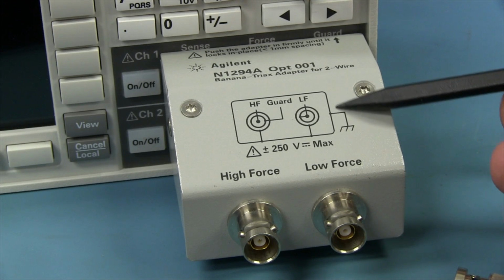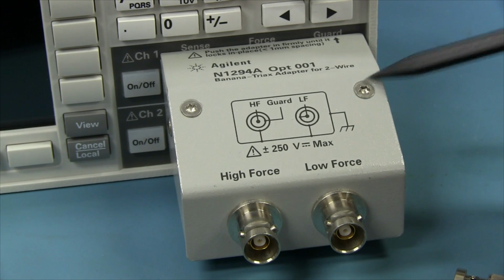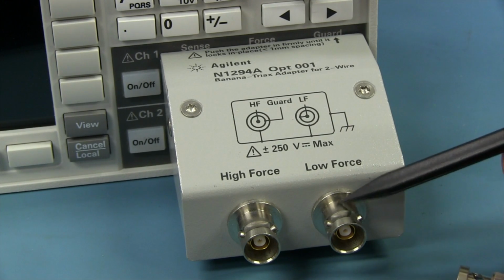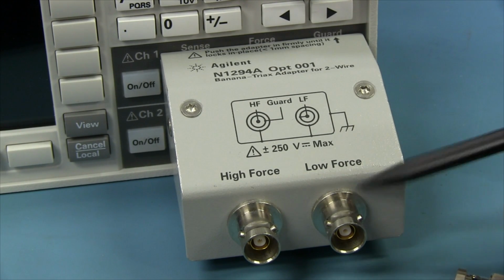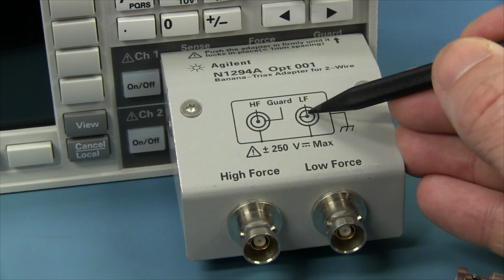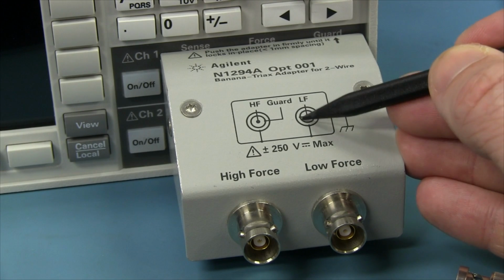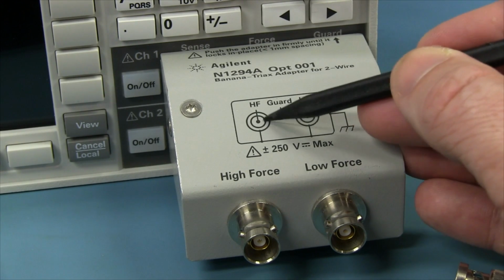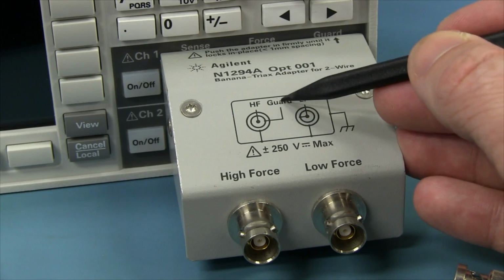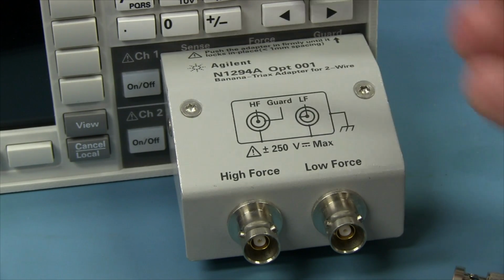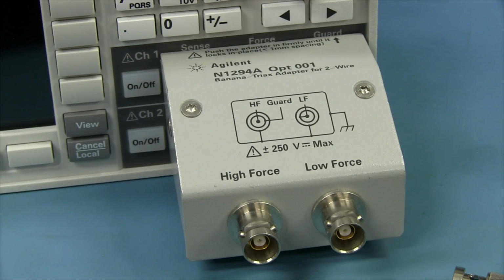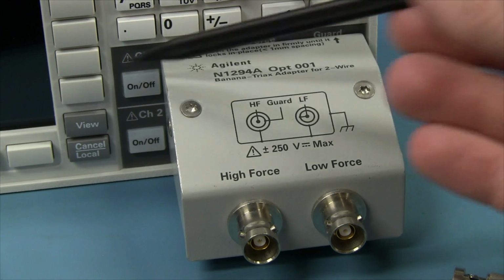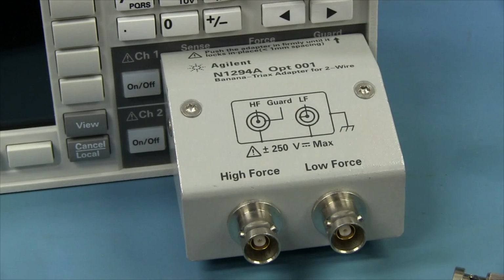And of course, you can see that this whole outer box, and the outer part of the coax, is connected through to your mains earth, so that stops any mains hum getting in. And then inside your triaxial, the shield inside there is connected through to your guard terminal, which is your circuit common inside your instrument. So therefore, you get double shielding on this thing, 50 hertz plus your protection, plus your shielding through to your ground inside the instrument. And that's how you do proper measurements on these sorts of very low current bits of gear.